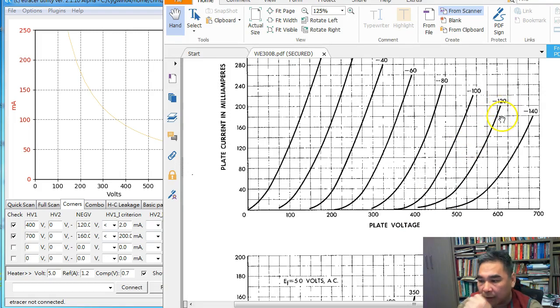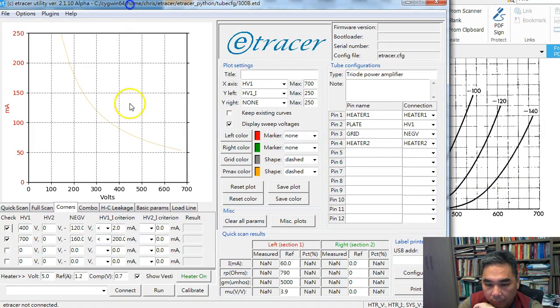For the cutoff current detection, I use 400 volt and minus 120 volt on the grid. The condition is: at this test point, the measured current cannot be higher than 2 mA. This captures the early rise of measured current at high voltage.